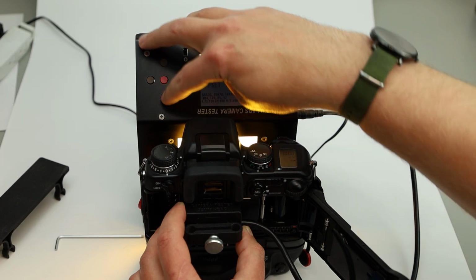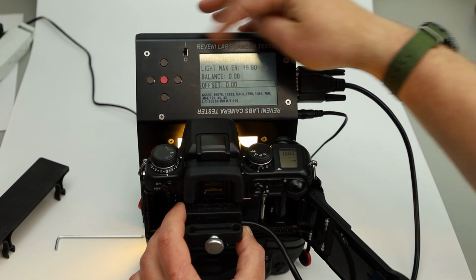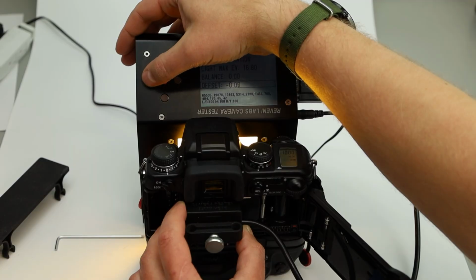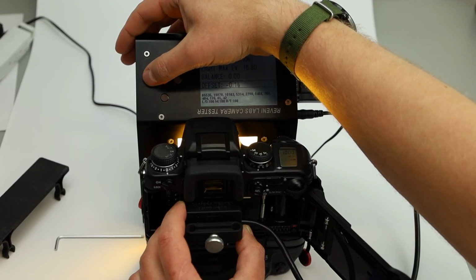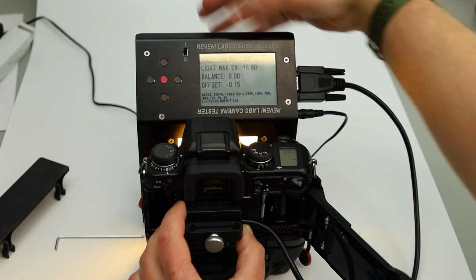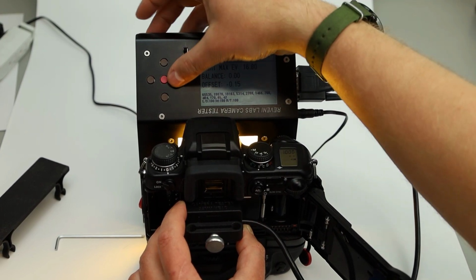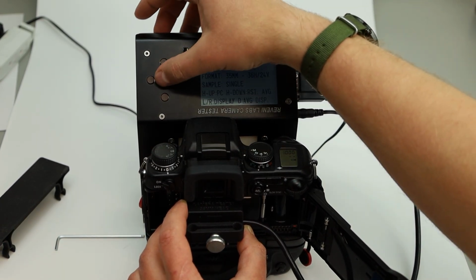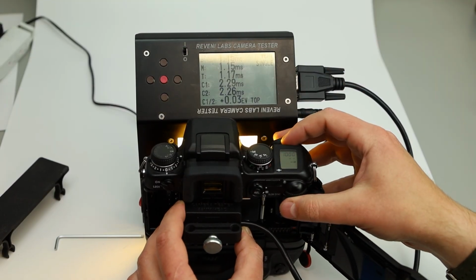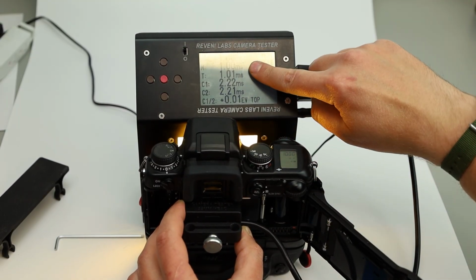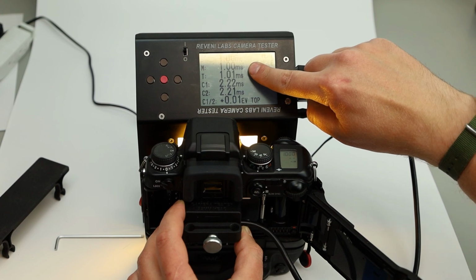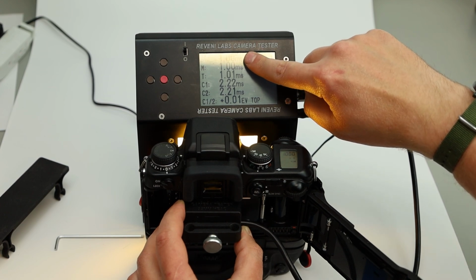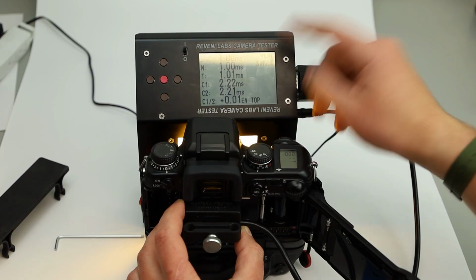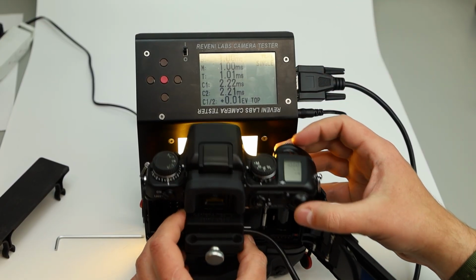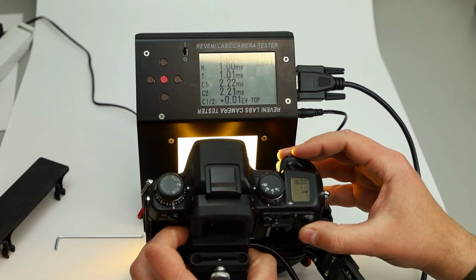So I'm going to enter the menu, go to the calibration page, go down to the offset setting, change it to negative 0.15, go back up to the top option, switch back to curtain shutter mode, press enter. Now when I fire the shutter, the middle is reading 1.0, bottom is also reading 1.0, top is reading 1.01. That's perfectly acceptable.